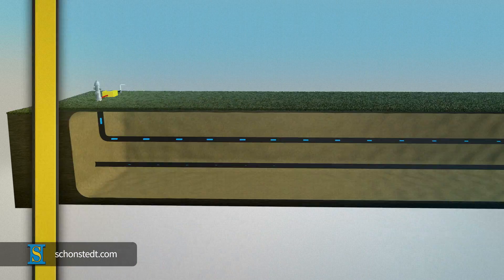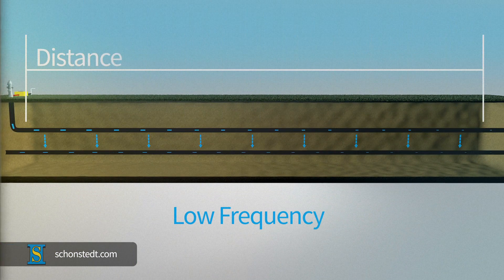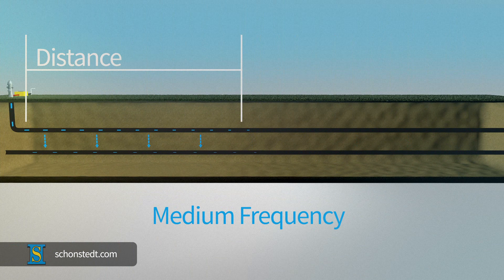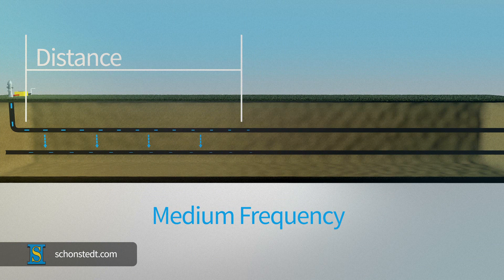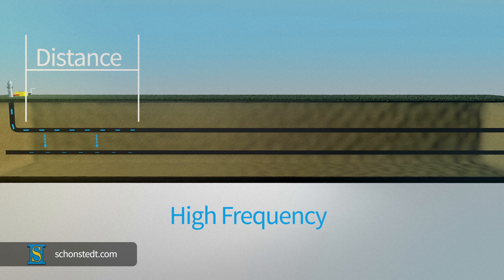As a rule, always start with the lowest frequency possible and increase as needed. And remember, at higher frequencies, the current will leak to the ground quicker, which may impact your ability to accurately locate.